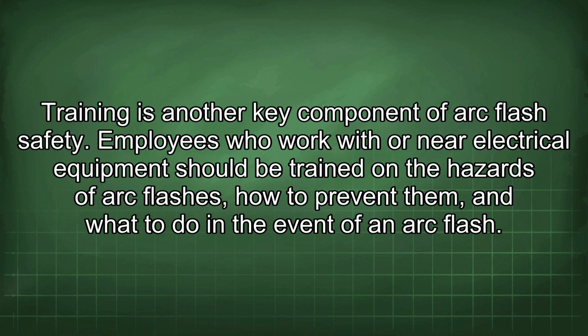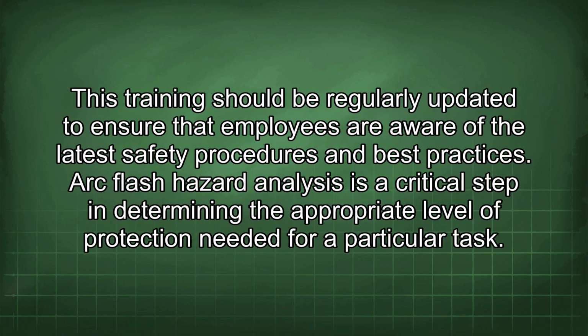Training is another key component of arc flash safety. Employees who work with or near electrical equipment should be trained on the hazards of arc flashes, how to prevent them, and what to do in the event of an arc flash. This training should be regularly updated to ensure that employees are aware of the latest safety procedures and best practices. Arc flash hazard analysis is a critical step in determining the appropriate level of protection needed for a particular task.